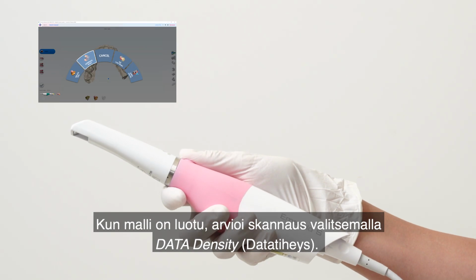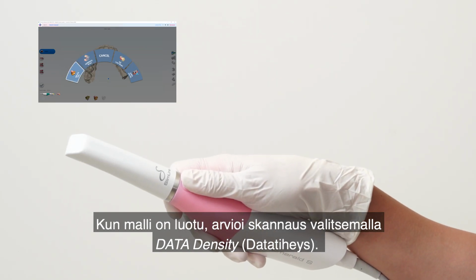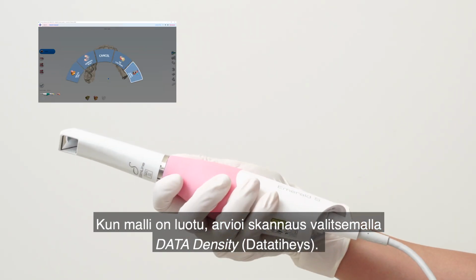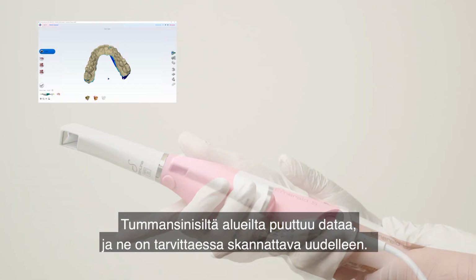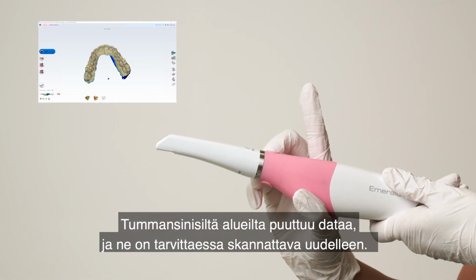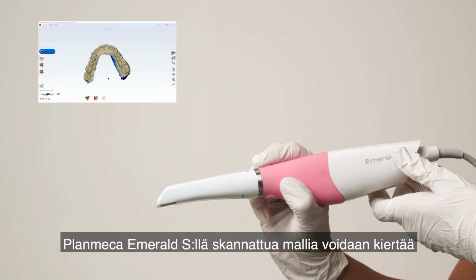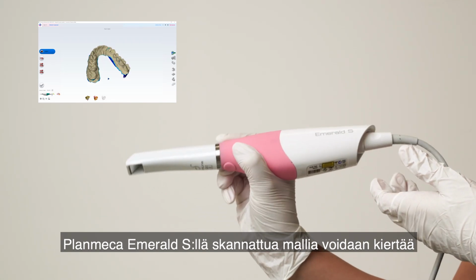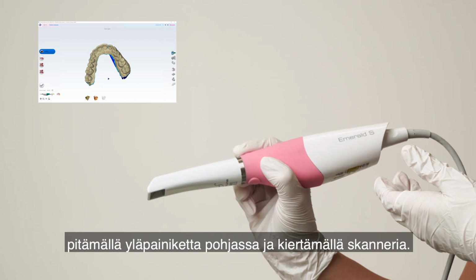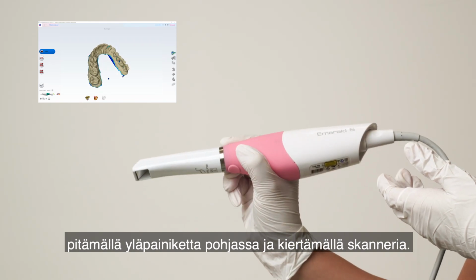After generating the model, evaluate the scan by selecting Data Density. Areas which appear dark blue are missing data and should be scanned again. In Planmeca Emerald S, the scanned model can be rotated by pressing the upper button and rotating the scanner.